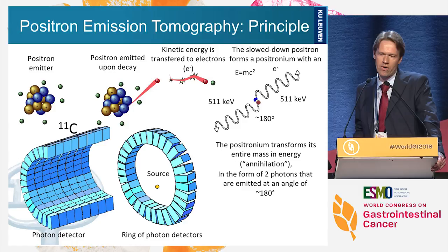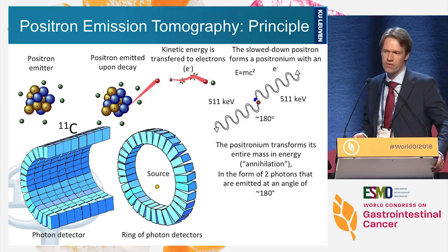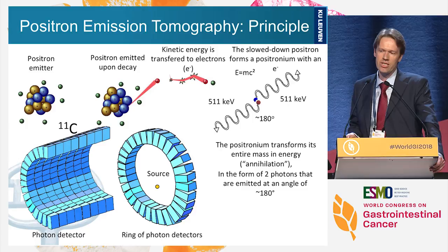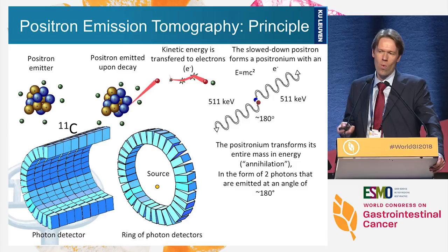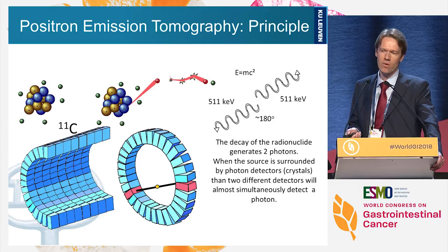Positron emission tomography, PET, uses positron emitters, which are radioactive atoms that upon decay will emit a positron. This positron will get rid of some kinetic energy and then annihilate with its counterpart, an electron, sending out two high energy photons of 511 keV. If we put a ring of crystals sensitive to these photons around the source, when two crystals get hit at almost the same time, we know that one annihilation event has taken place on this so-called line of response.